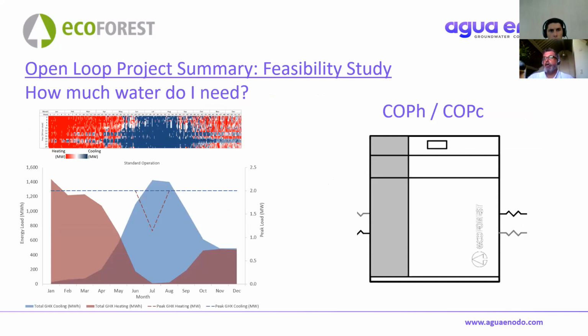Here we've plotted the heating and cooling loads for a rather large system we were looking at in London. Months go across the top - this little plot looks like a QR code, doesn't it? A little pixelated heating and cooling chart. We've got hours in columns for every day down the y-axis. You can see we've got heating dominant in winter, and around June, July, August we've got this cooling-dominant blue in the middle. That's typically the level of information we like to have to start designing our open loop system.